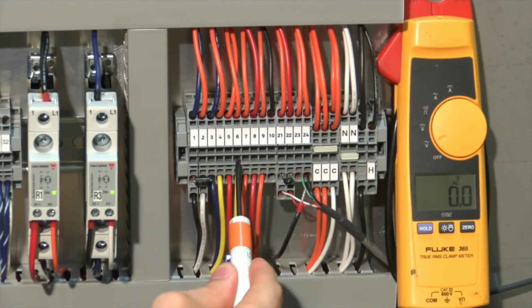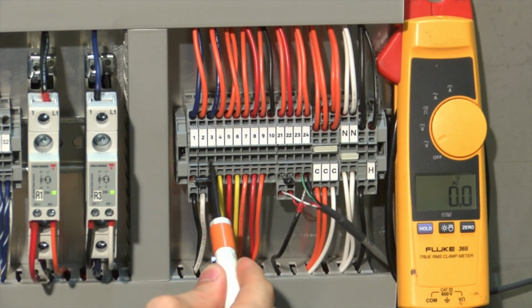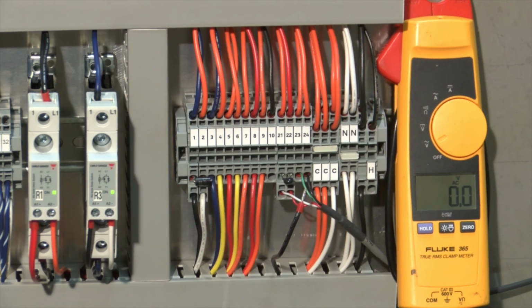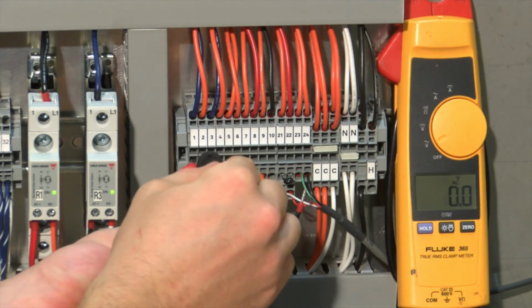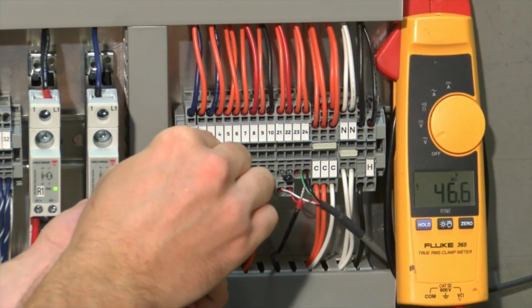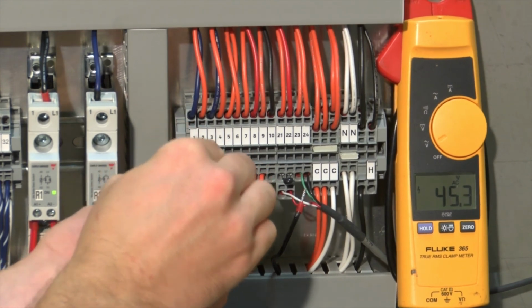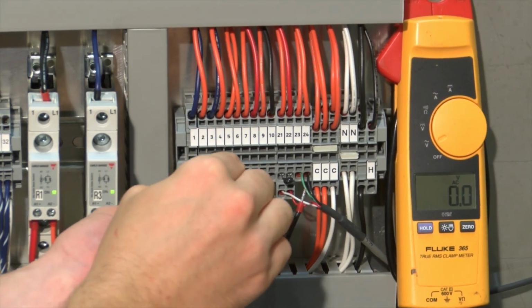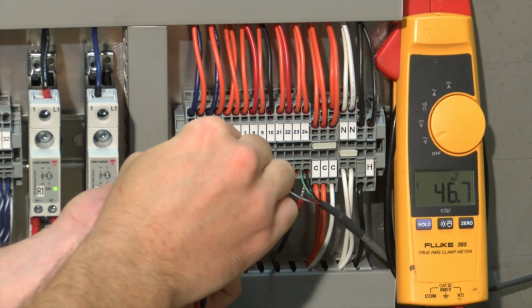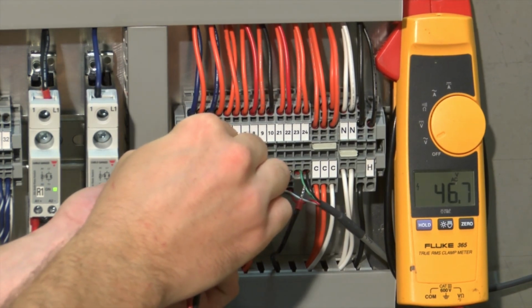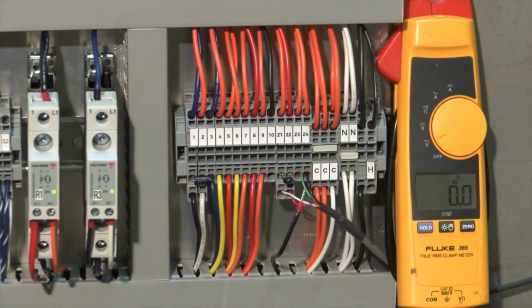The small openings in the middle of the terminal blocks are used to make contact with the circuit. Having your voltmeter set on AC, we can take a reading at terminal 1 and 2 and see our 48 volts. We can take a reading at 3 and 4 and see our 48 volts for row B. If these terminals are powered by 48 volts and your transducers are still not operating, the transducers themselves may be failed.